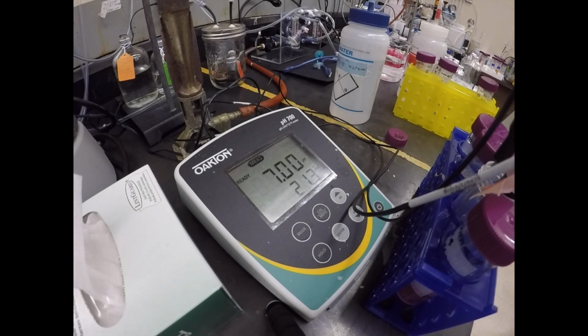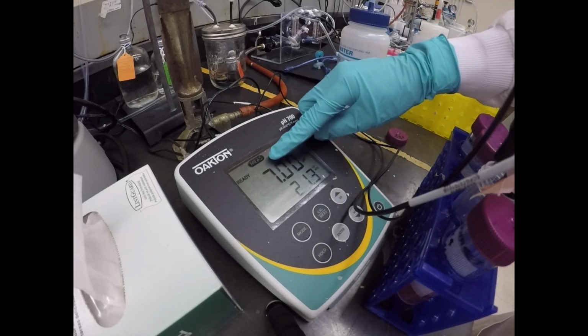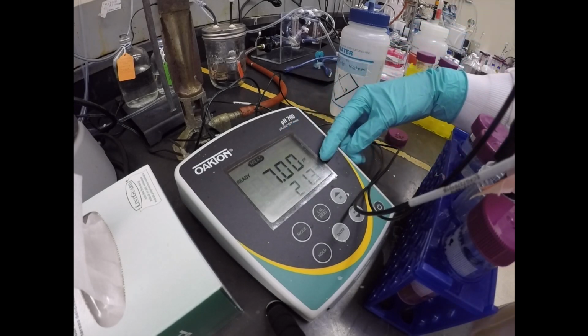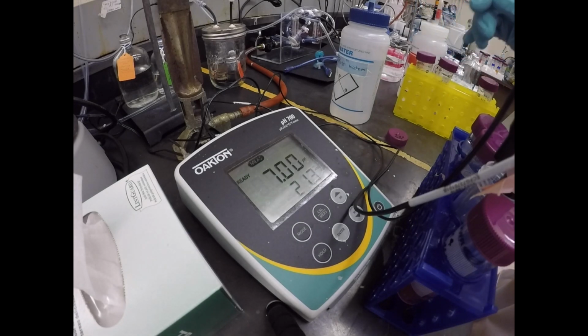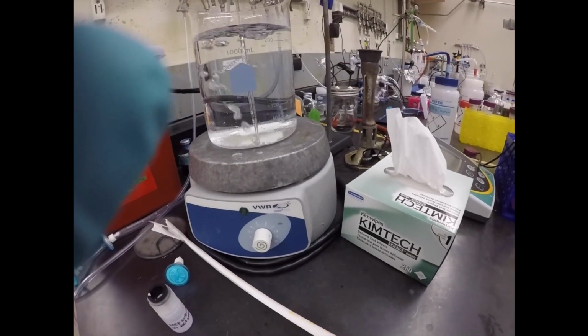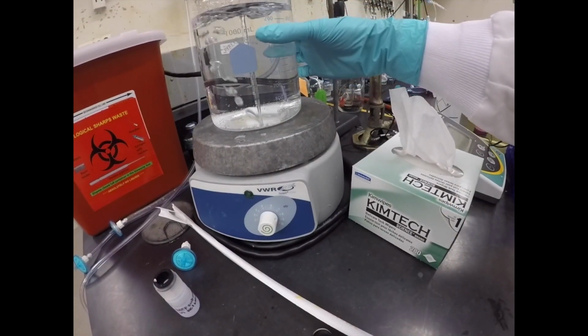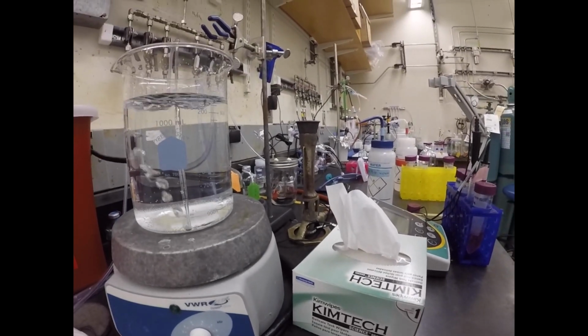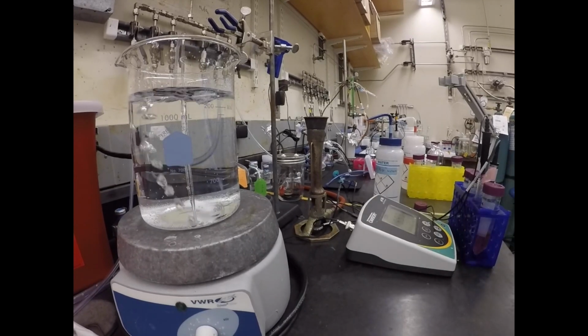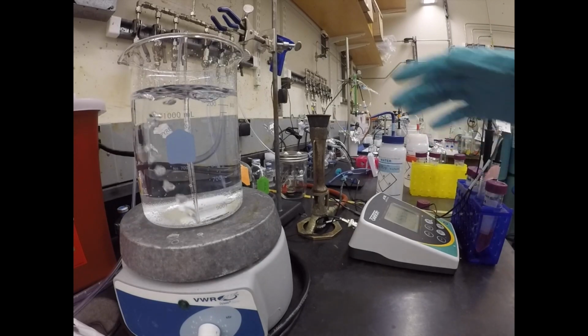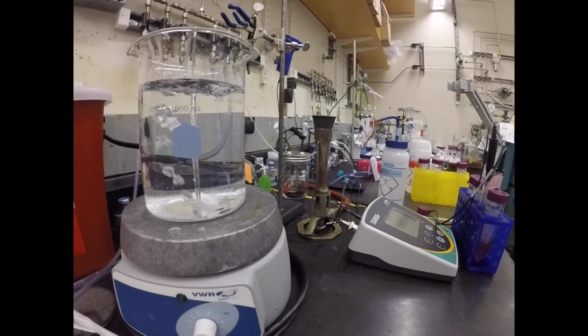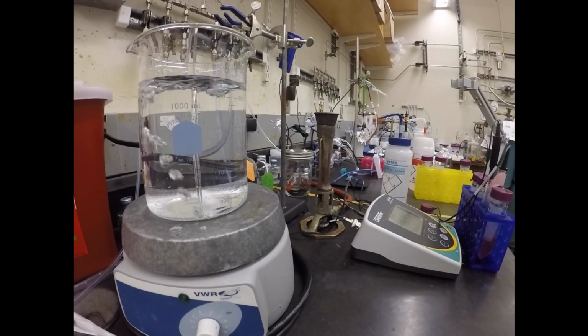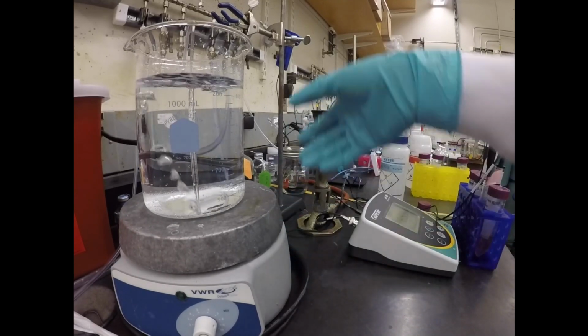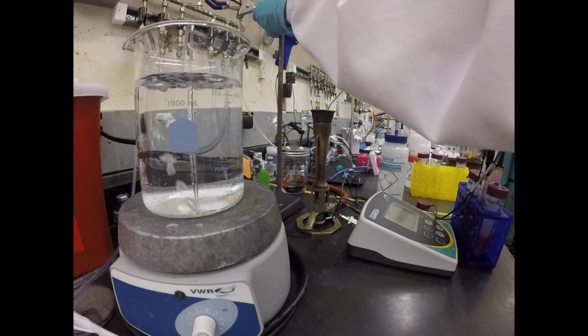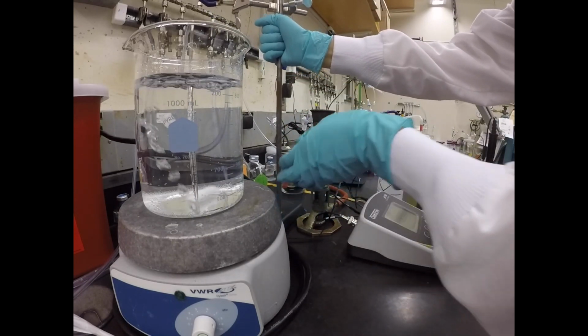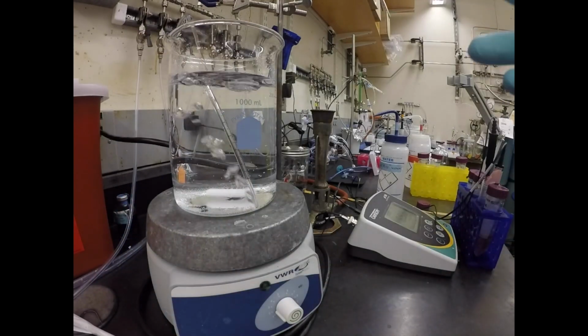Alright, so the calibration is done. Now I've switched back to the measurement mode, as you can see there, and in the pH 7 solution it is reading 7.00. So it is ready to go. Now I'm going to place the pH and temperature probe in suspension in this medium, and to do that I usually just use a simple trick with lab tape to hold these probes in place in an optimal position. Because the stirring plate is adding a little bit of height, I'm going to use this ring stand to kind of hold the pH and temperature probes.